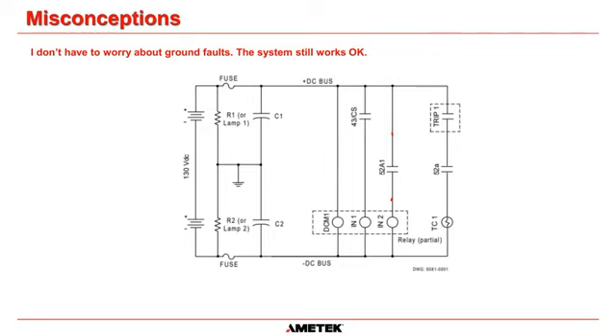And I think this is the last misconception. I don't have to worry about ground faults. The system will still work okay. And in truth, that is a true statement, because one of the reasons we have a floating system is that if we do have a ground fault, then the system will still work without any issues in most cases. Okay, there are some exceptions.